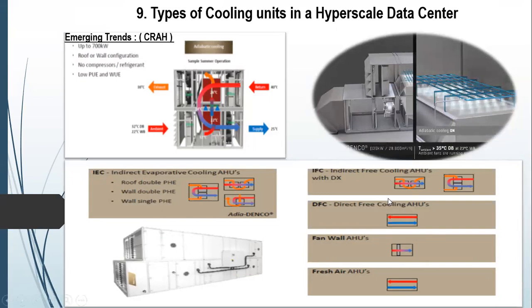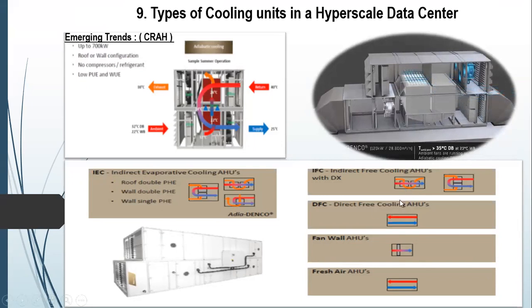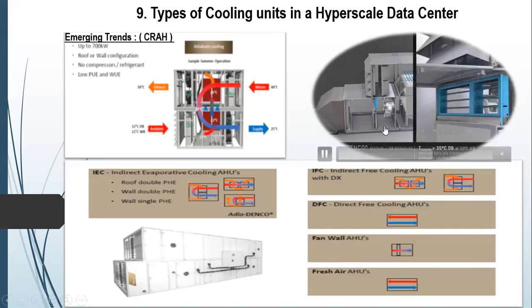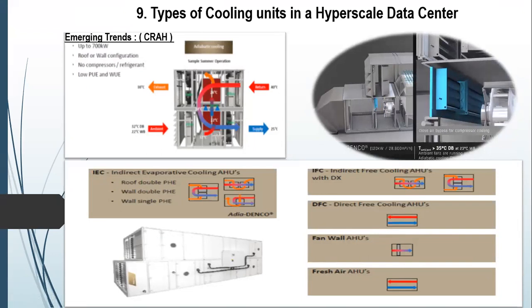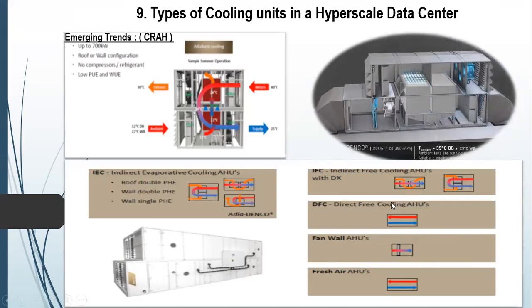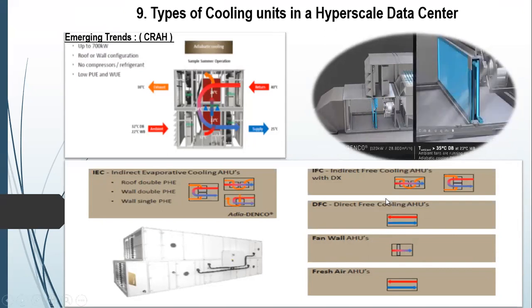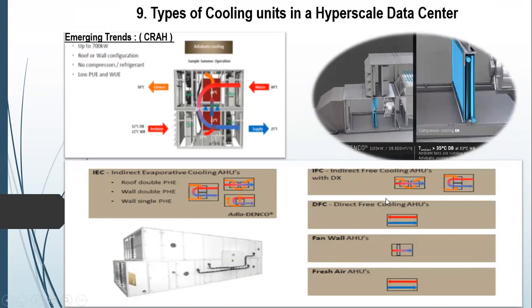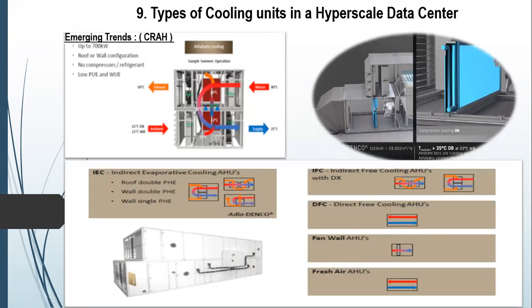Here, as we see, higher the ambient, there is a cooling pad which sprays the water, and then you have the benefit of lower temperature entering. In this case, all the components are working. The compressor, the fan, the cooling pads are all operational. These can also be connected to a chiller. As the ambient drops, one of the components one by one would shut down, and then only the fan or the cooling pads would get operational as per the requirement of the DC space.